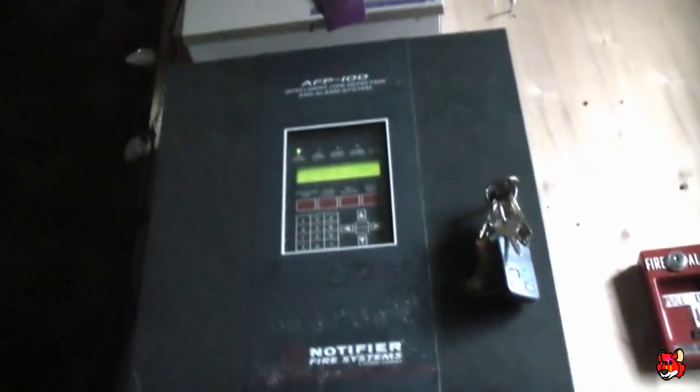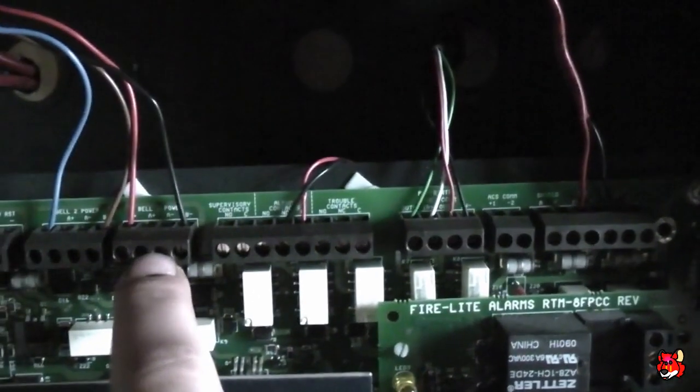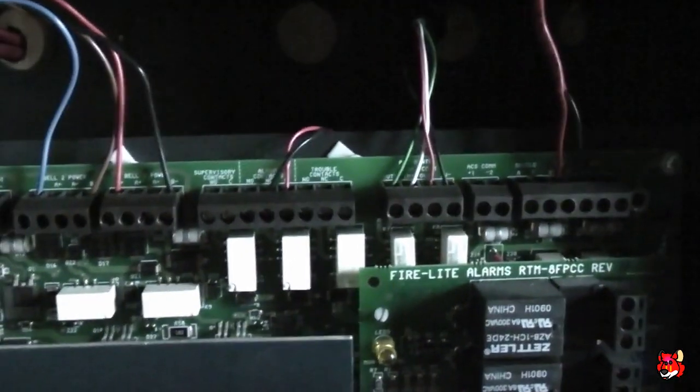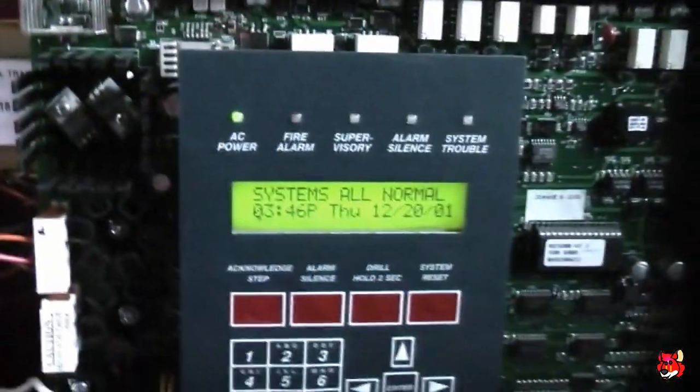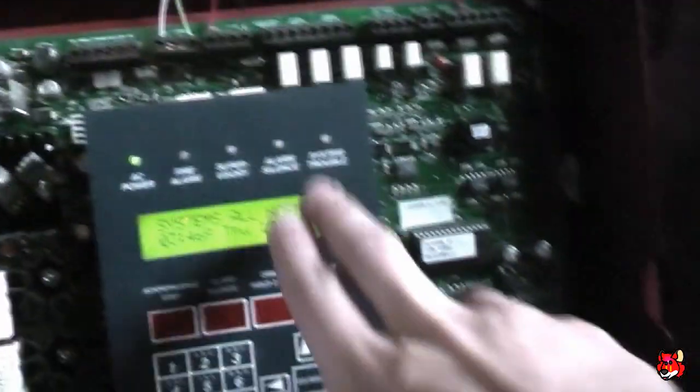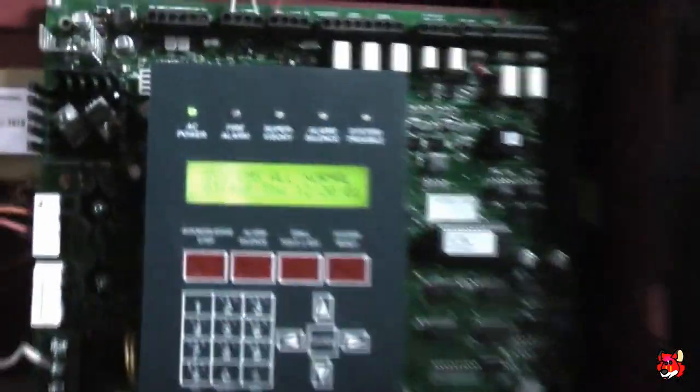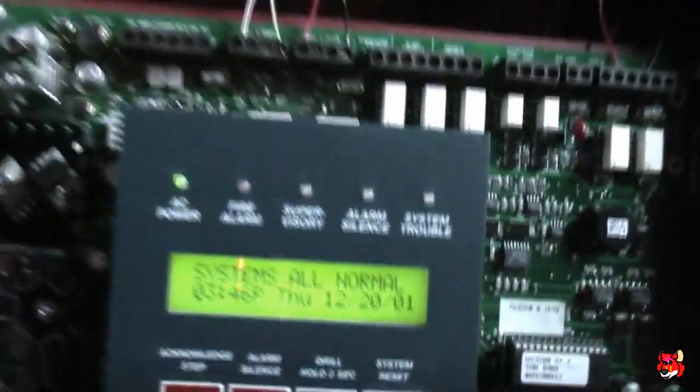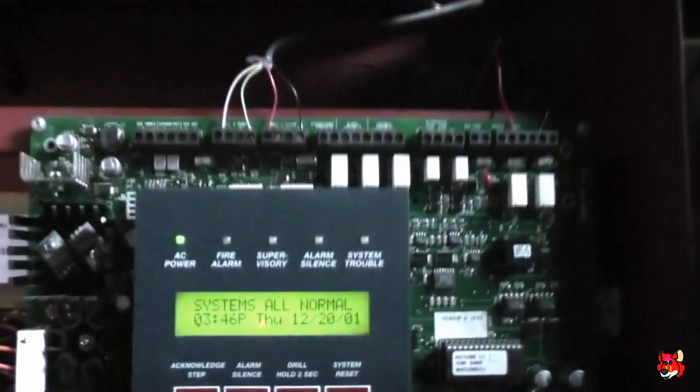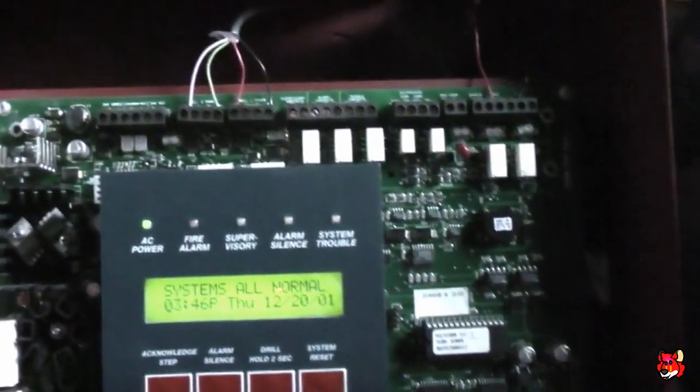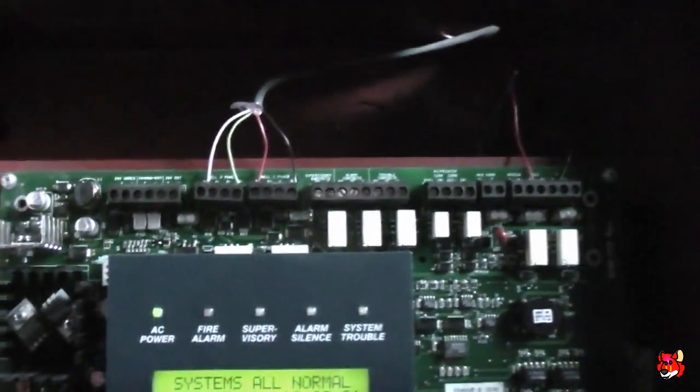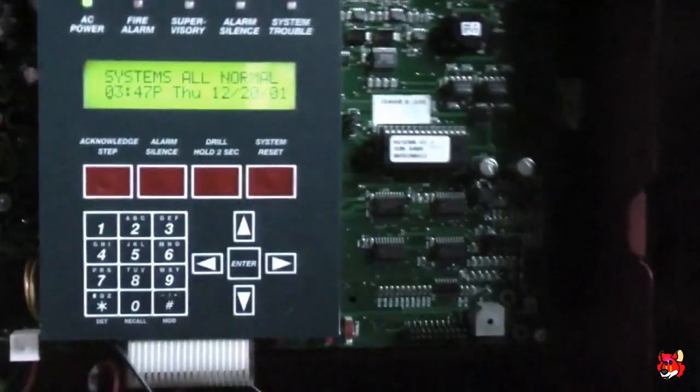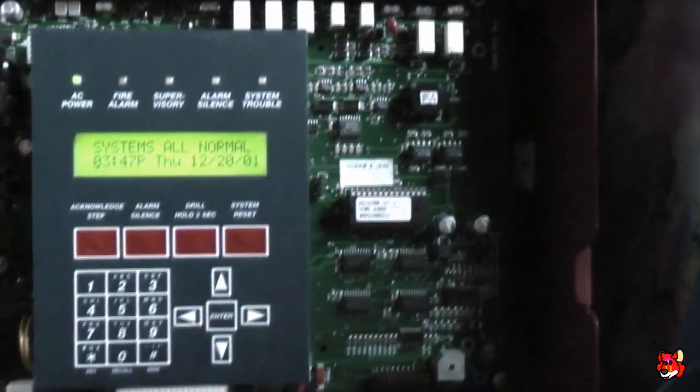And actually, in a way, it works better than this. Because, for some reason, NAC1 on this panel is not detecting a resistor. And I'll probably demonstrate that in a later video. But it doesn't detect a resistor. This one does. I don't know why this one doesn't anymore. It might be an issue in the programming, but I'm not sure. Because the NACs are programmed exactly the same on this one. Bell Circuit 2. Strobe only. Bell Circuit 1. Horns.